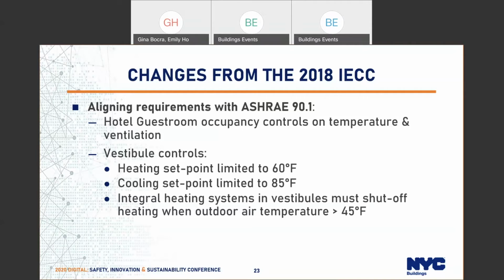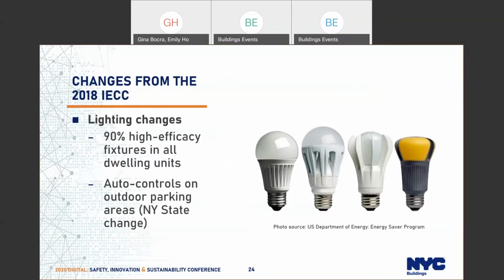So for vestibules, the heating set point cannot exceed 60 degrees Fahrenheit. And the cooling set point in vestibules cannot go below 85 degrees. And then for integral heating systems, whenever the outdoor temperature is greater than 45 degrees, it has to shut off. So really, this is just preventing overheating and overcooling within vestibules, and again, aligning with 90.1. So those were the highlights of the changes from the state code for HVAC.